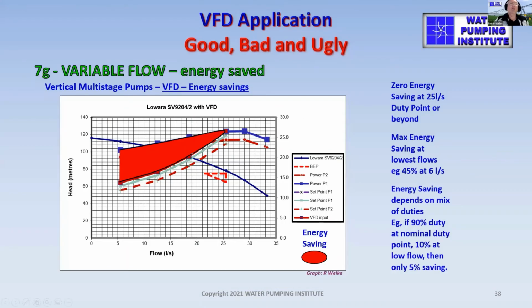Let's have a look at a graph of energy saving. If we were to draw a power curve for a normal pump, so this is your head quantity curve, the blue curve here, and this other blue curve with the square dots represents the power over the range. And if we were to put a VFD on it at this point, with a type B pump, and run the pump at a constant pressure along this line, this would be the energy saving in here. So it graphically demonstrates, most of the time in a turf situation, we're running the pump system up here, and so there's no tangible savings at all for 90% of the running time in a turf situation. Where you do benefit is that you don't get over pressurization, therefore misting and water wastage when you go down to the lower flows.